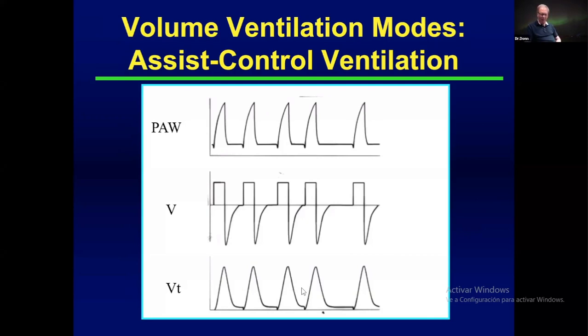And this just shows you a volume delivery in assist control. Again, we're looking at this square flow waveform and the delivery of tidal volume. And remember, with assist control, each time the patient meets the trigger threshold, there is going to be the delivery of a mechanical breath that is timed to synchronize with the baby's own breathing. And here you see a typical combination. These two breaths are rather close together, and these two breaths are further apart. Again, showing you the variability in the baby's own spontaneous breathing and how the ventilator will follow that pattern of breathing.